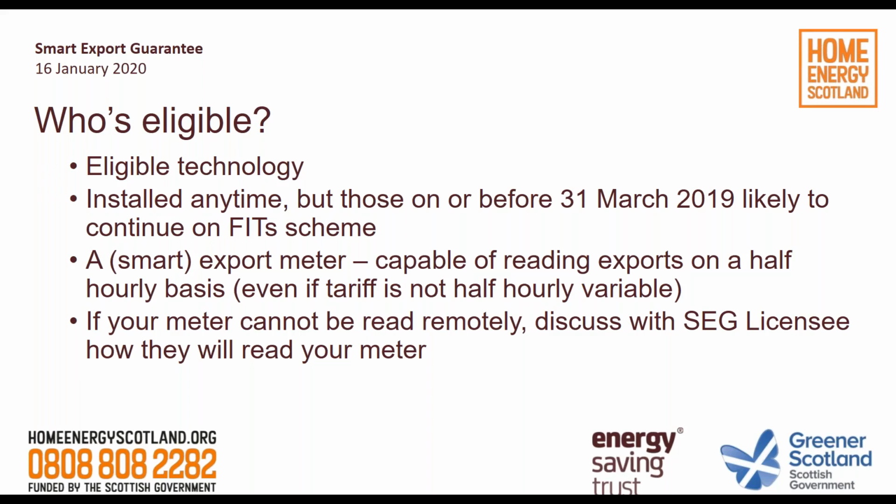You'll also need a smart export meter. It needs to be an export meter that is capable of reading exports on a half-hourly basis. Even if your tariff isn't paying you for every half hour, your meter needs to be capable of that. If you don't have one, you'll need to speak to your energy supplier about the install. If your meter cannot be read remotely, so that you're not able to send your readings to them directly, again, discuss with your chosen SEG licensee how they'll go about reading your meter and whether they can. If they can't, they aren't obliged to under the SEG rules, so it's worth chatting to them about possible routes for that.